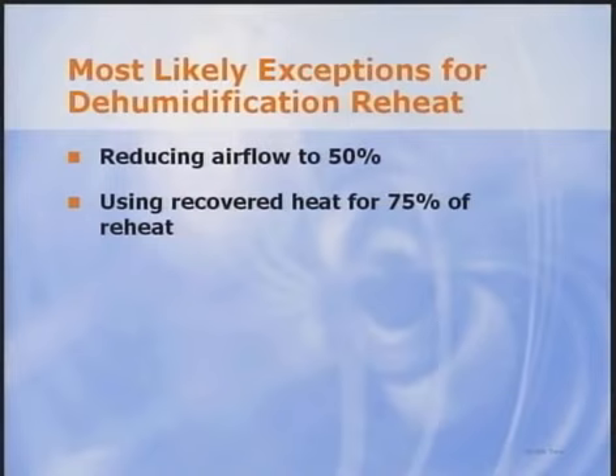However, if you decide to use supply temperature reset and have humidistatic controls to ensure proper space humidity levels, you need to either reduce the airflow to 50% or recover the energy used for reheat. I was in Puerto Rico in September of this year discussing humidity control, and heat recovery has been used for years there to minimize energy use. At 25 to 30 cents per kilowatt hour for energy costs, there's a real incentive to recover heat.